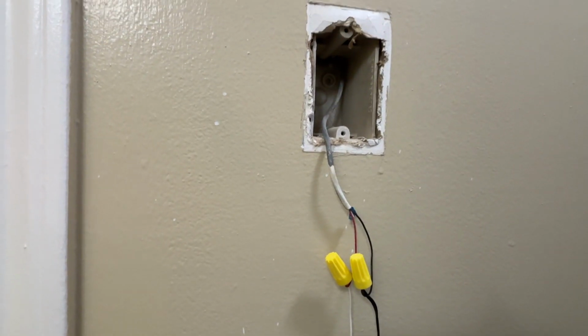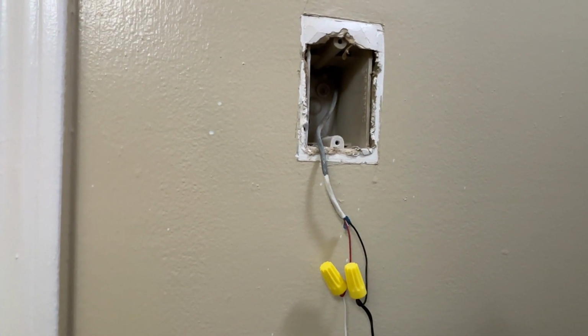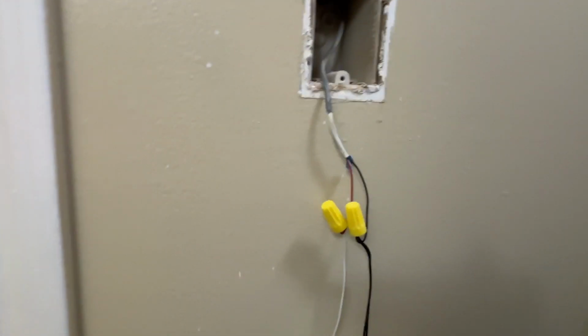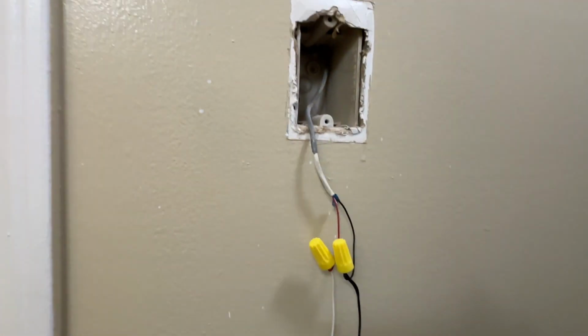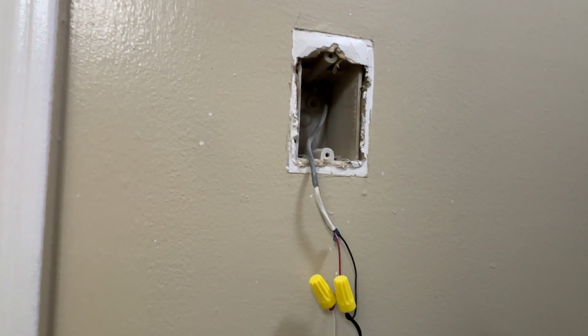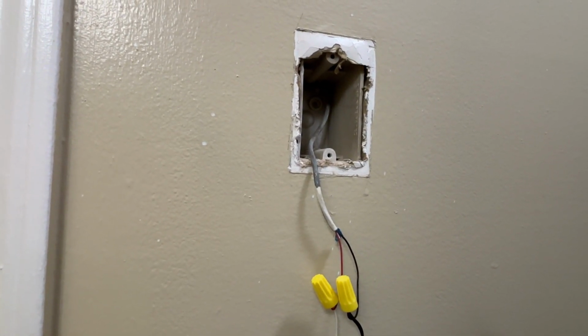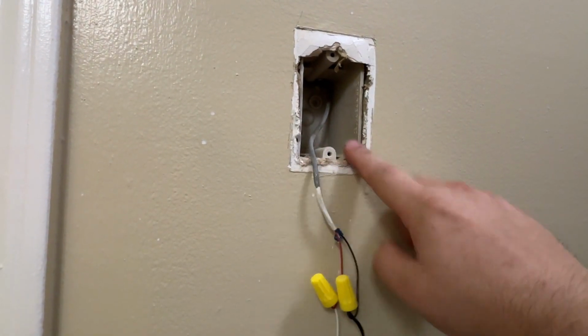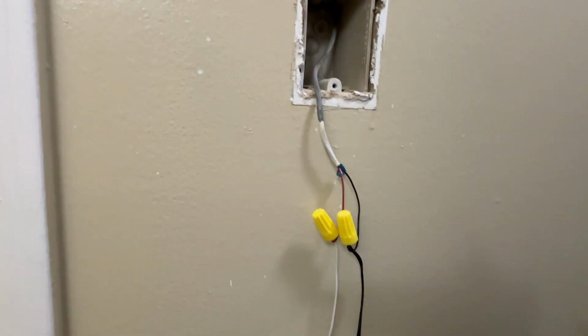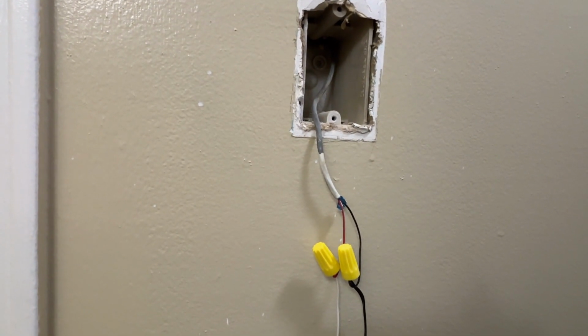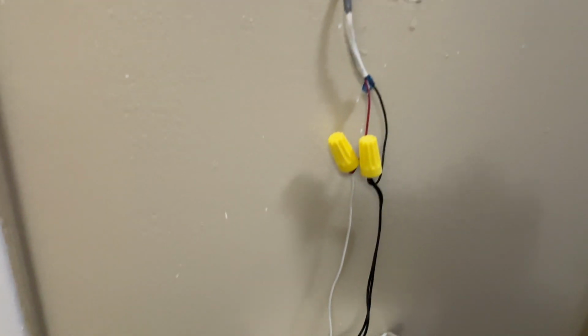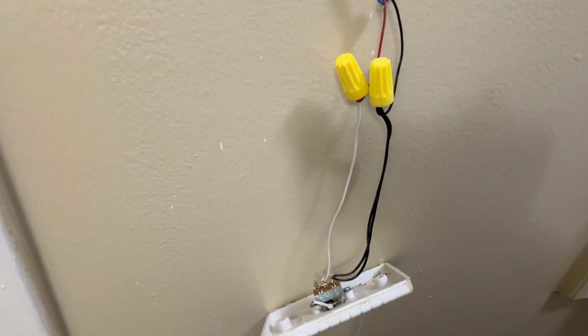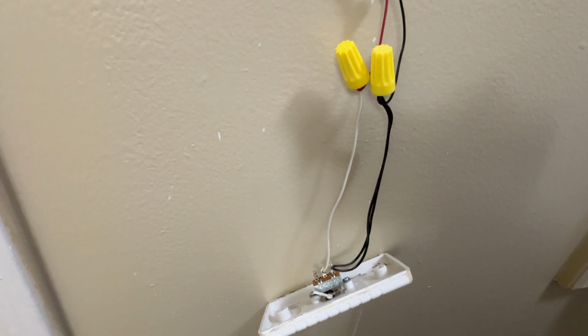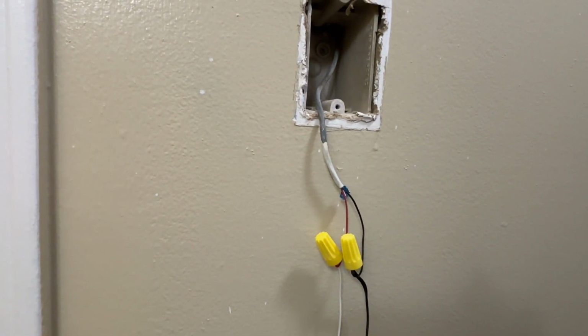This unit only has one run of low volt wire in each junction box for each emergency pull cord switch. The junction for these is out in the hallway behind our strobe where you've seen that big mess of wires. However, some units will have two runs of your low volt to where they pigtail off of this switch, which means you need to test each switch in your unit to verify they're all working. If you have one that is pigtailed and it is sending the power from this switch to the next switch, if this switch is bad, then that would cause your siren not to strobe.